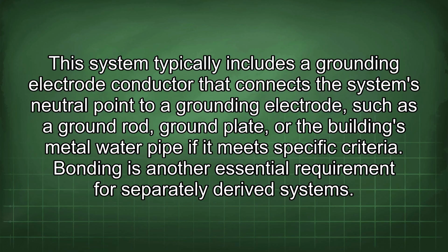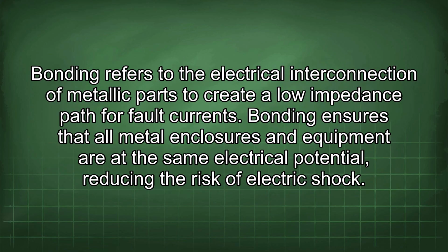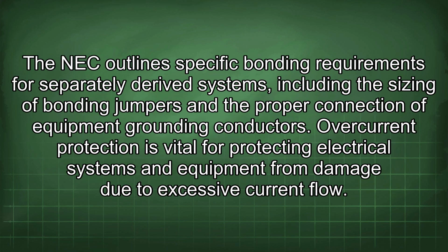Bonding is another essential requirement for separately derived systems. Bonding refers to the electrical interconnection of metallic parts to create a low impedance path for fault currents. Bonding ensures that all metal enclosures and equipment are at the same electrical potential, reducing the risk of electric shock.